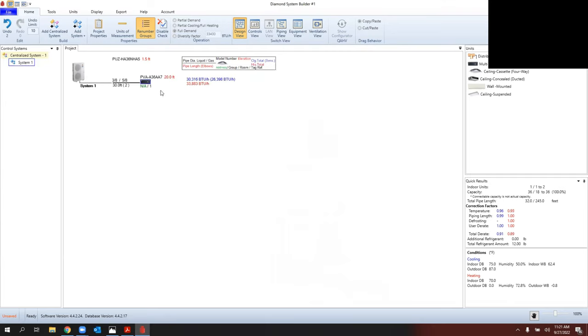I hit OK, and it pops up the condenser picture with total cooling at our design conditions. For this three-ton system, we'll get 30,316 total BTUs per hour, with sensible at 26,398 — the difference being latent. In heating at our design conditions — which I believe was zero in Worcester — we get 33,883 BTUs. It de-rates slightly due to line set length and being a bit below five degrees, where we get 100% capacity on Hyper Heat. However, without a controller selected, you can't export.